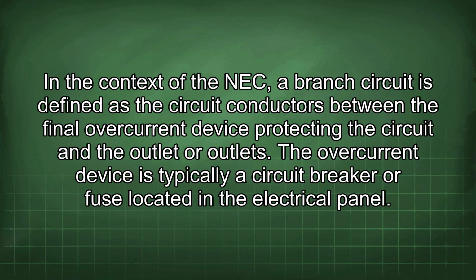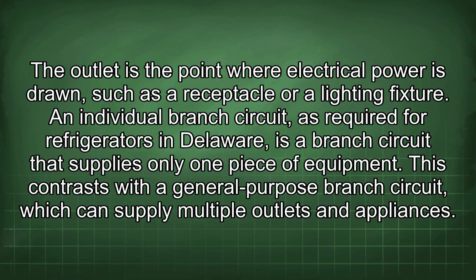In the context of the NEC, a branch circuit is defined as the circuit conductors between the final overcurrent device protecting the circuit and the outlet or outlets. The overcurrent device is typically a circuit breaker or fuse located in the electrical panel. The outlet is the point where electrical power is drawn, such as a receptacle or lighting fixture. An individual branch circuit, as required for refrigerators in Delaware, is a branch circuit that supplies only one piece of equipment. This contrasts with a general-purpose branch circuit, which can supply multiple outlets and appliances.